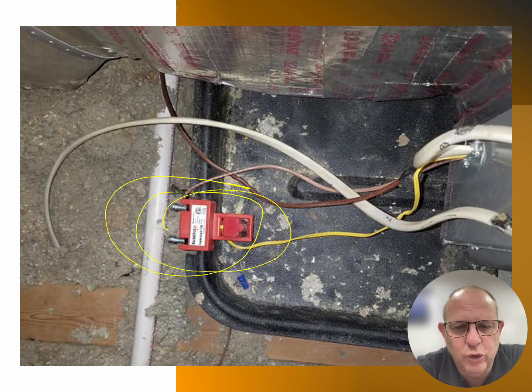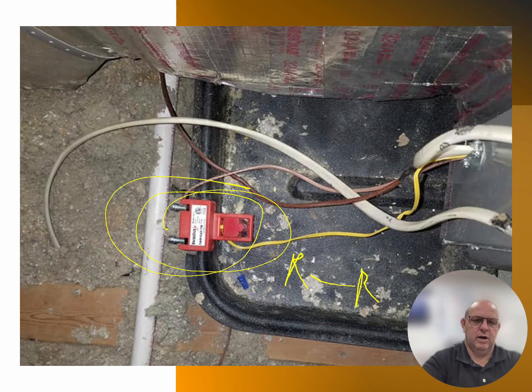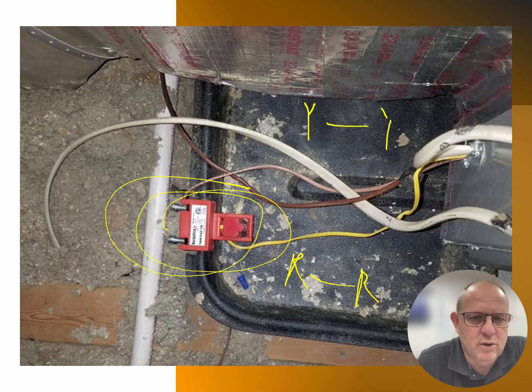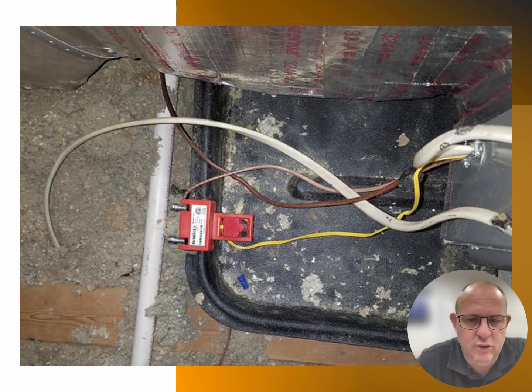Now, there's a couple of different ways we can tie this in. These wires are running over. I can tie them to the R and hook it in series with the R so it breaks that. I prefer not to do it that way. I will probably come across with the Y terminal from the indoor unit and then hook it in series with the Y terminal on that indoor unit. So it shuts off the outdoor unit, but the indoor unit is continuously running. The customer will notice that there's a problem and will give you a call to fix that problem on that particular unit.